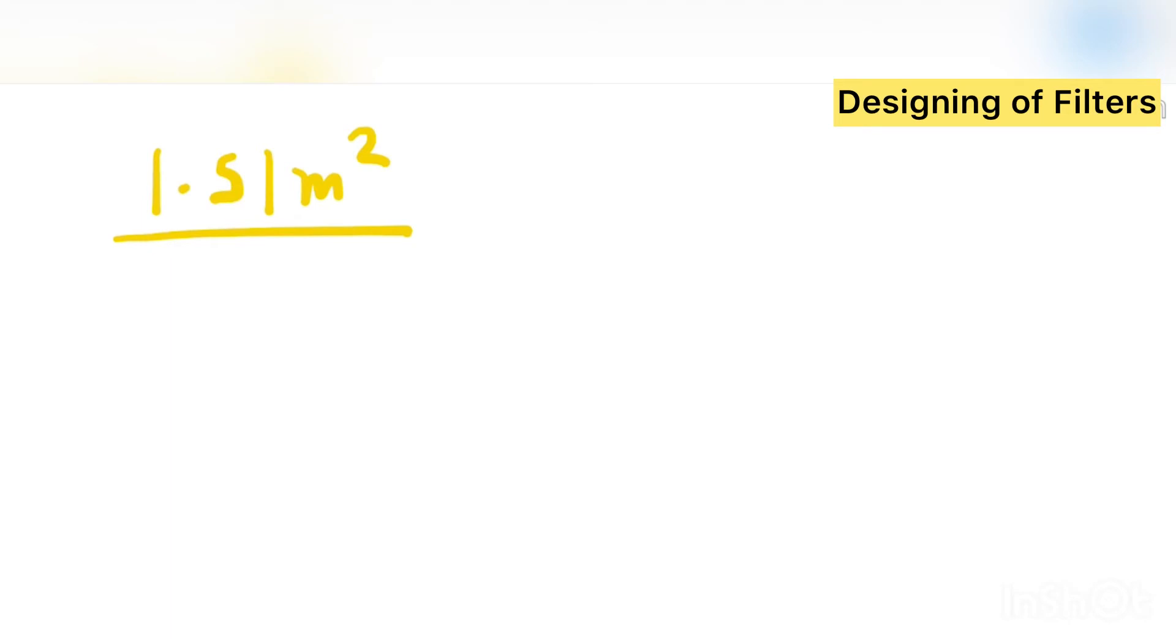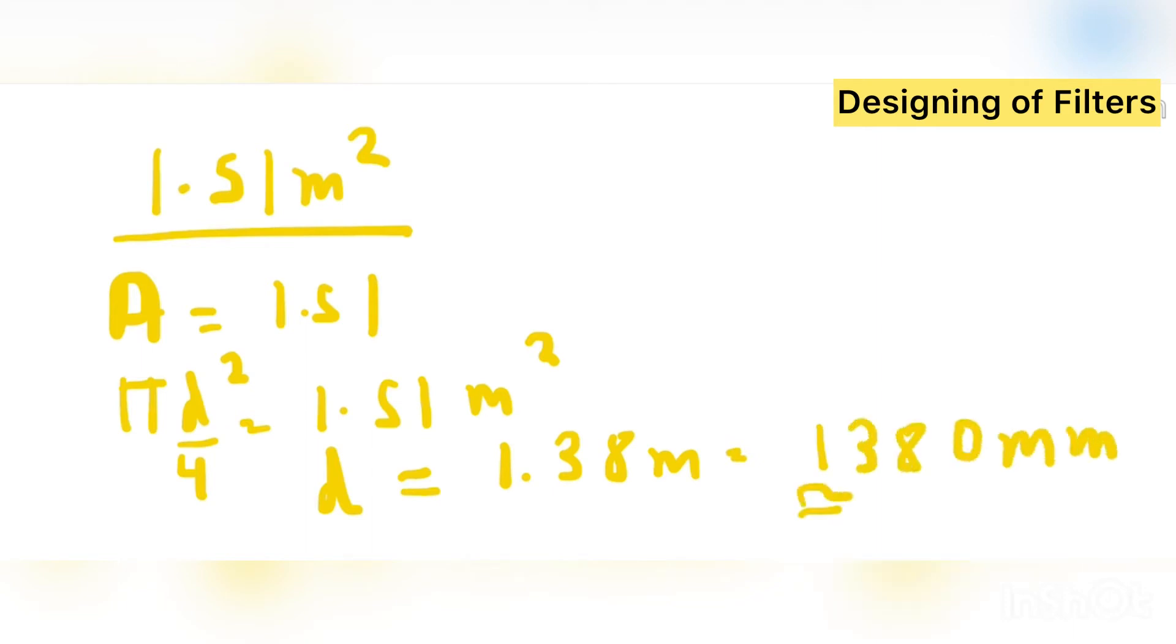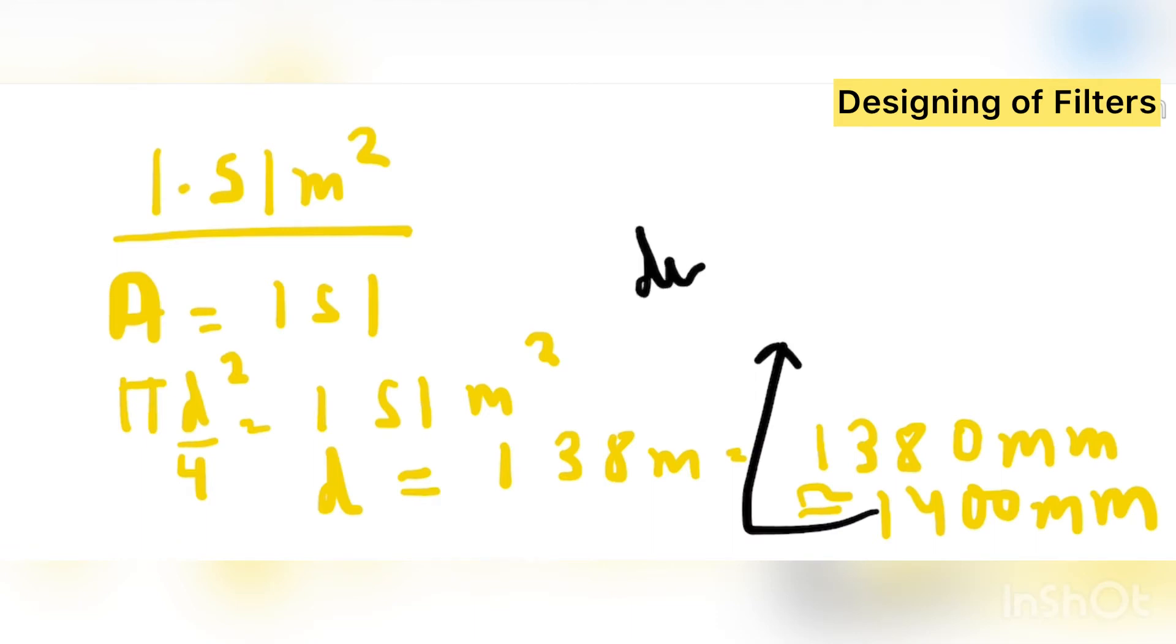So this is the area of filter we require. Now as we know that area is coming is 1.51, so pi d square by 4 is equal to 1.51 meter square. So we can arrive from the d. So what is the d we can arrive is if we solve this 1.38 meter or 1380 mm. So approximately we can say 1400 mm is the diameter.